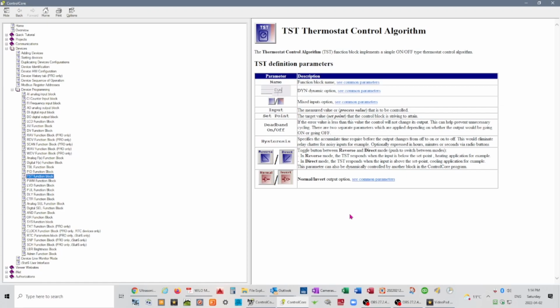You're not stuck with a manufacturer's proprietary thermostat control. You are basically building it from scratch and telling the thermostat what to do based on the inputs and what to act on based on those inputs, and how to respond to internal temperatures, when to respond. In other words, the dead bands: how much do you let the temperature go above and below the set point. It's amazing the control that you have over the system based on using this ControlCore software that ThermAtlantic have incorporated into all of their devices. They've used this protocol to create the functionality of their devices, and it's just not available in any other manufacturer's products.